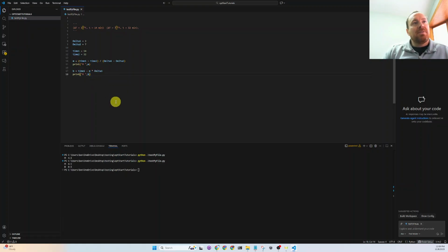Even though it's fake data, it would be what we would add to our calculation to account for a little bit of lag in physics. So if you energize a cooling coil or turn on a boiler or a chiller, there's some lag in the system before you start seeing the effect on the temperature sensors. So this is what our intercept b would account for.